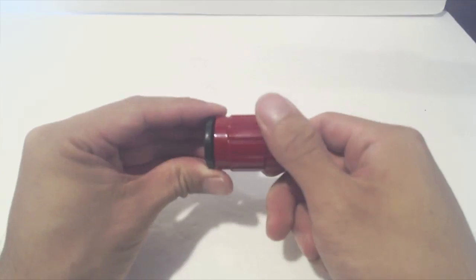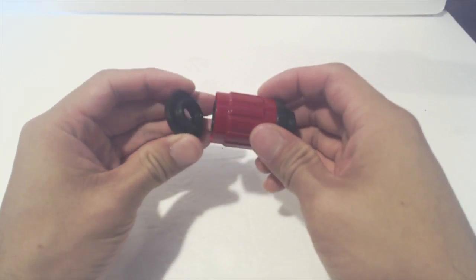Okay, so it seems like there's a fragment of something stuck in my viewing tube. I've unscrewed the eyepiece, and yes, it's here in this section. I'll take a quick look inside by unscrewing the top lens.